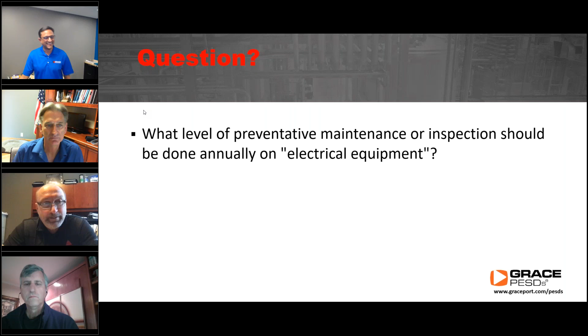Believe it or not, for molded case circuit breakers, the best maintenance you can do is exercising them, but guess what, no one does. Because one, you've got to shut off the power, and as you said, if it runs 24/7 we can't turn off the power. You have to find time where this maintenance, like exercising breakers, requires the power be turned off for minutes, not necessarily half an hour. So does anybody exercise their molded case circuit breakers? I bring this up when working with clients and they go, what? Something as simple as that - you have to be able to turn the power off and find a time when you can do it.